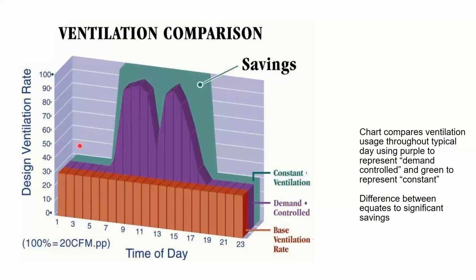So on a normal system, what happens is the building goes occupied at 7 o'clock in the morning or whenever it goes occupied. And then the fresh air intake opens up, and I bring in a certain amount of outside air, cubic feet per minute, and it stays there all day long. And then the building goes closed, and I shut it back down. When I put the CO2 sensors in, this is the purple line.